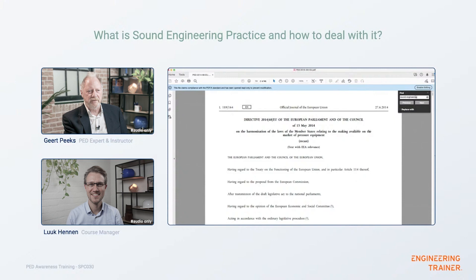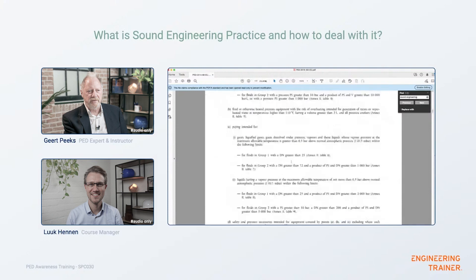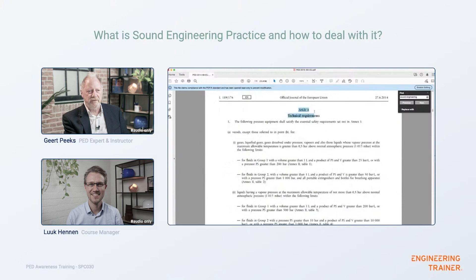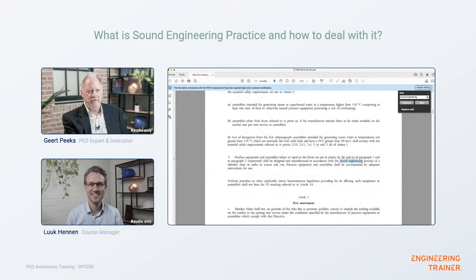In front of us we have the Pressure Equipment Directive, and in Article 4, technical requirements, item number three, it says: pressure equipment and assemblies below or equal to limits set out in points A, B, C of paragraph one and paragraph two respectively shall be designed and manufactured in accordance with the sound engineering practice of a member state in order to ensure safe use. Pressure equipment and assemblies shall be accompanied by adequate instructions for use. This is the first time in the Pressure Equipment Directive that the term sound engineering practice is used.